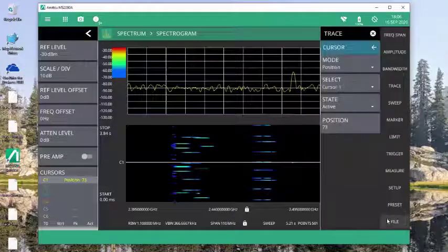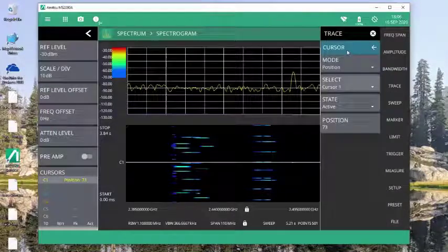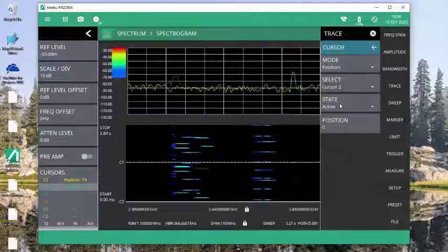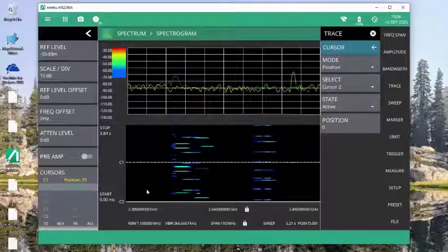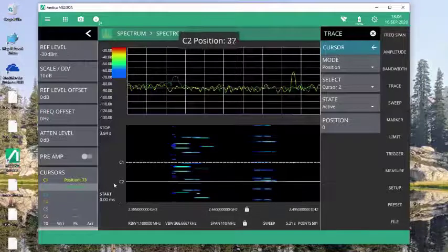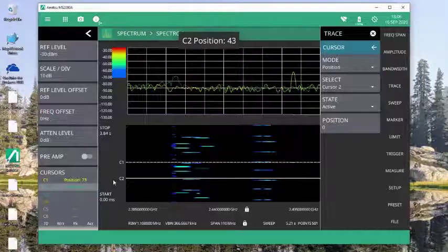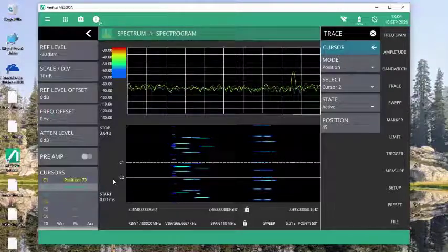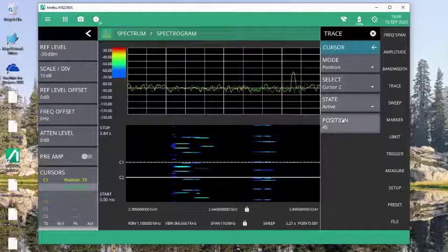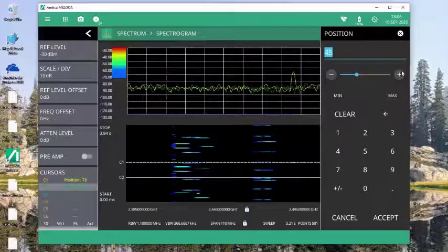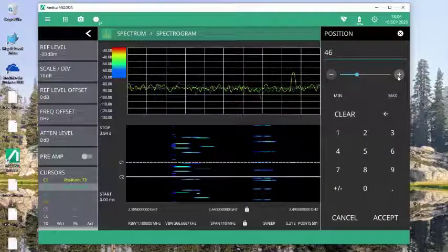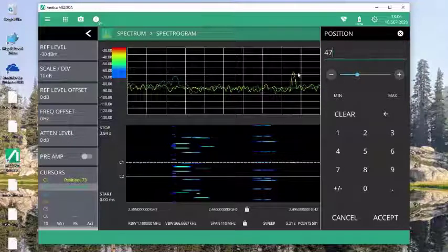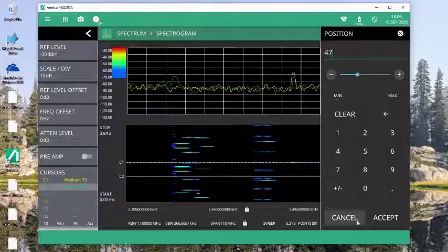I can also turn on a second cursor if I want. And again, with this second cursor, I can come through. I can make changes in the position. Let's see, I want to capture that other anomaly there. Simply increment it till I find it. There it is on that trace.